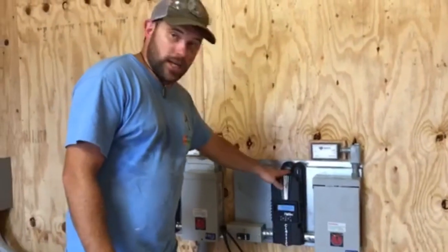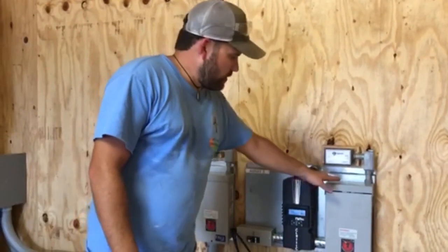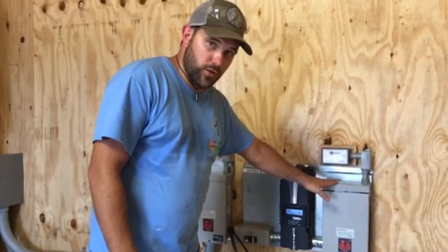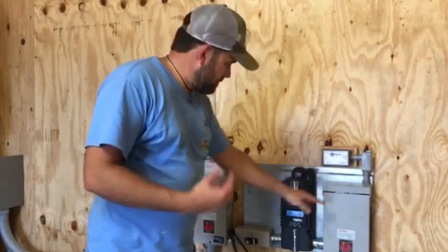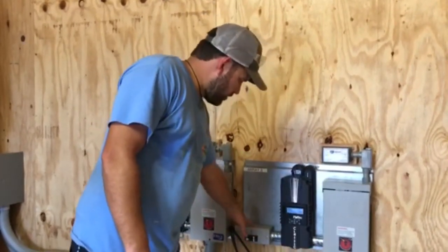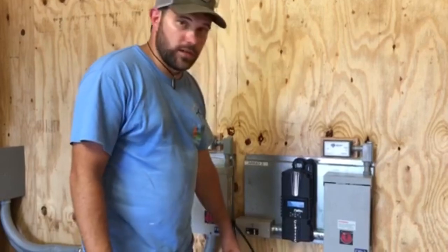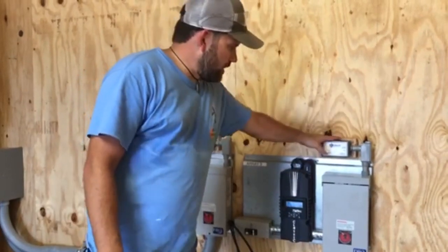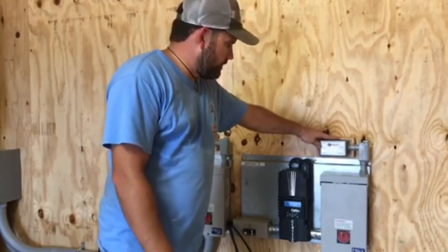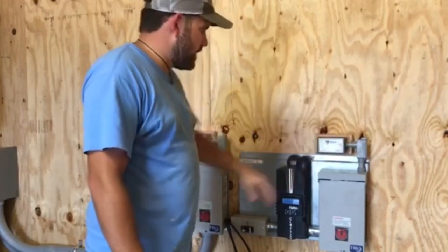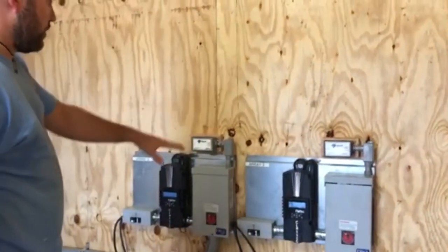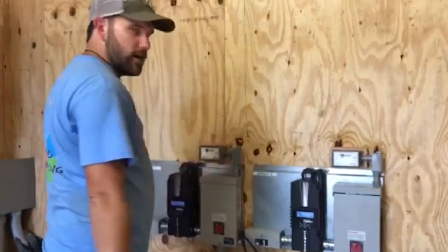Now what you have is a MidNite Classic charge controller, the combiner box for all your solar arrays coming in, and then the breaker protecting that unit between the battery bank. This is the new EMP shield, as described earlier in the video. Every one of those units has that, and it goes out to a ground rod shared on that array.